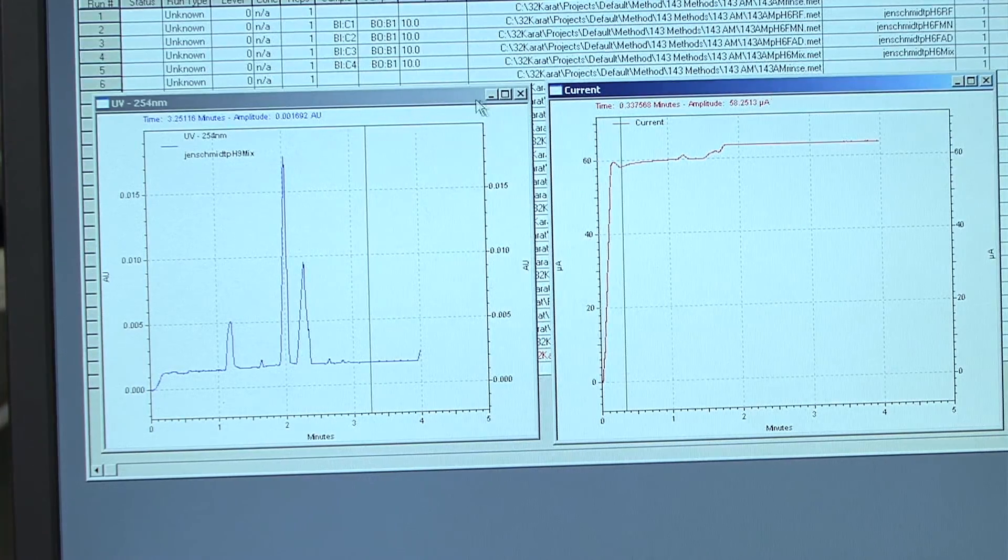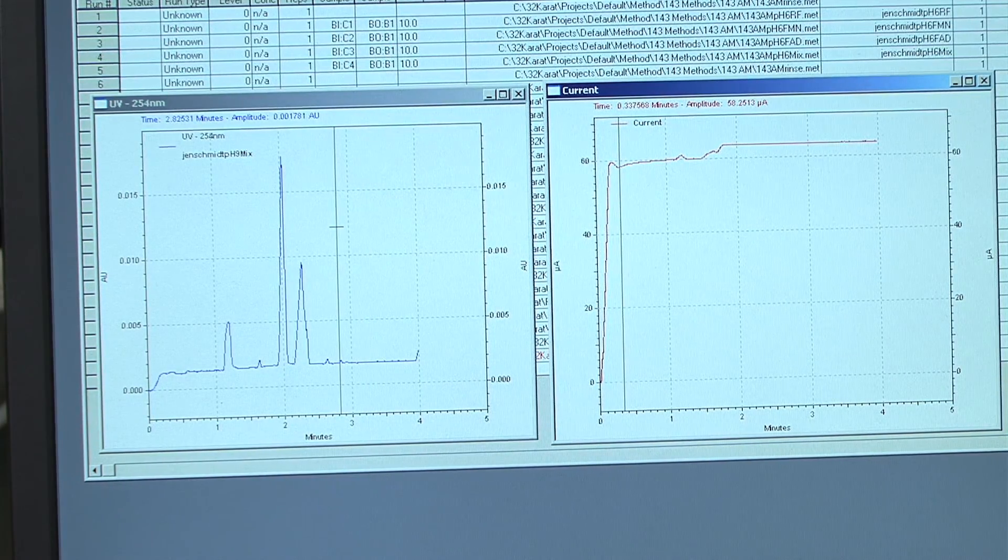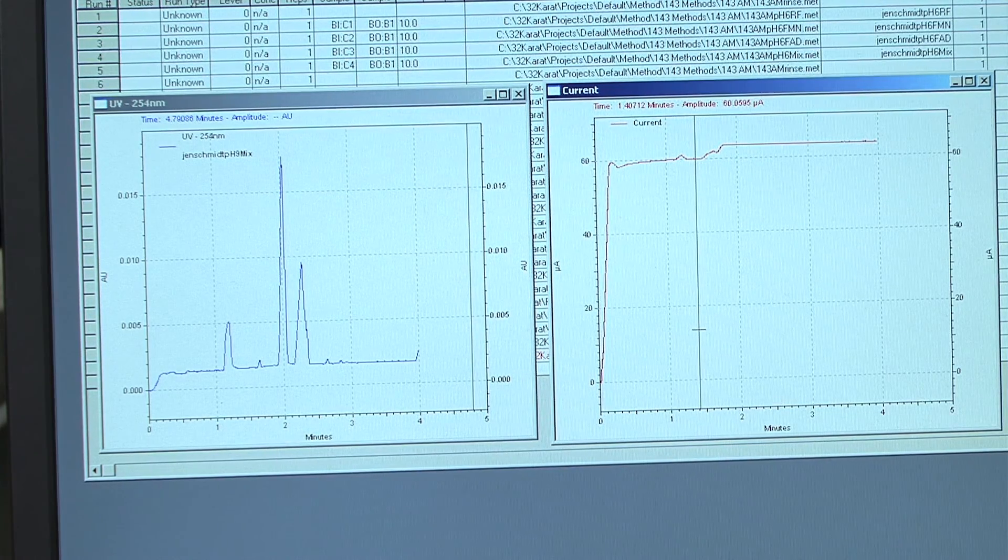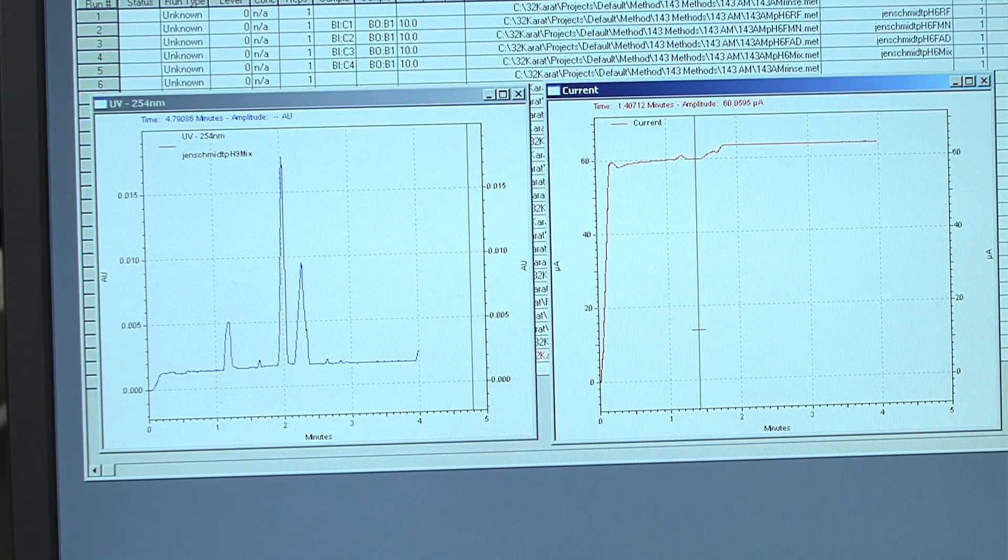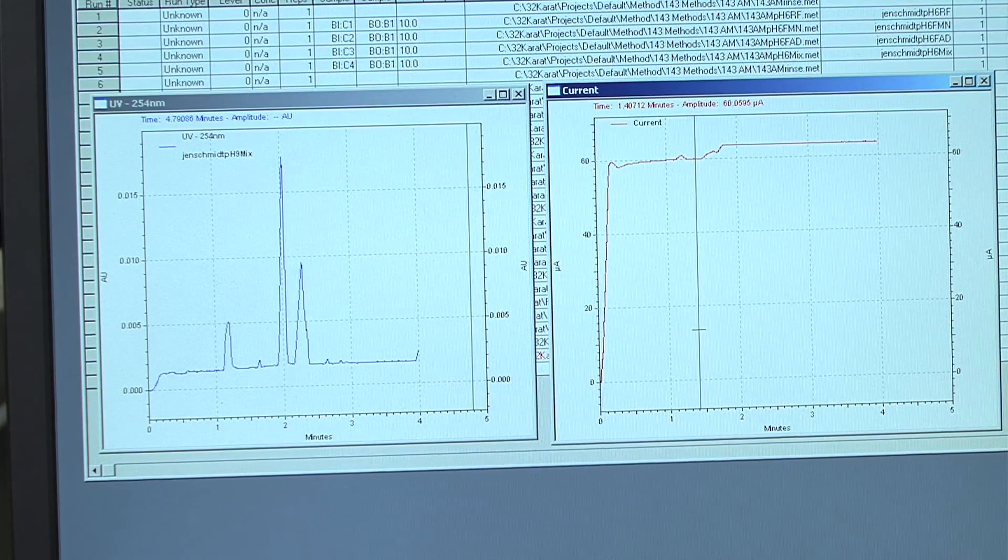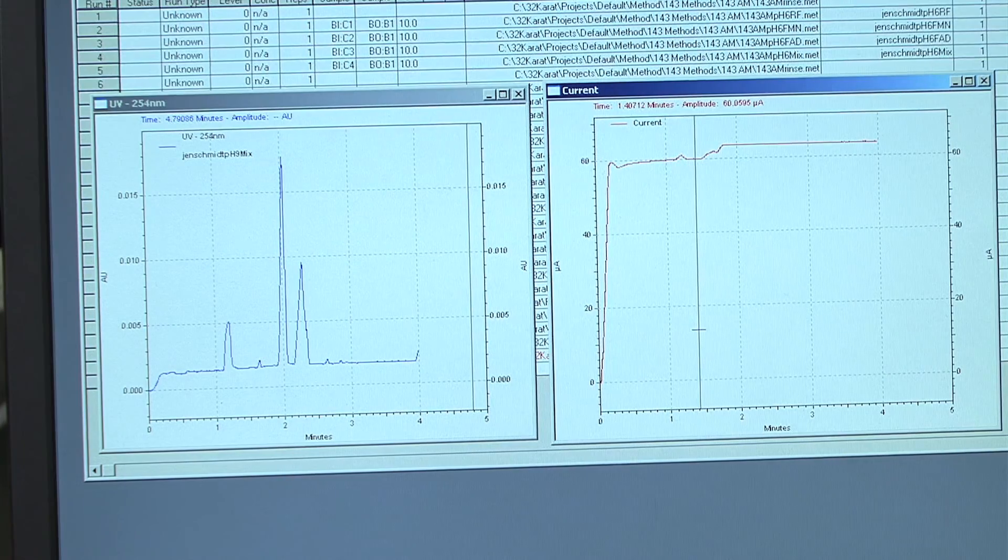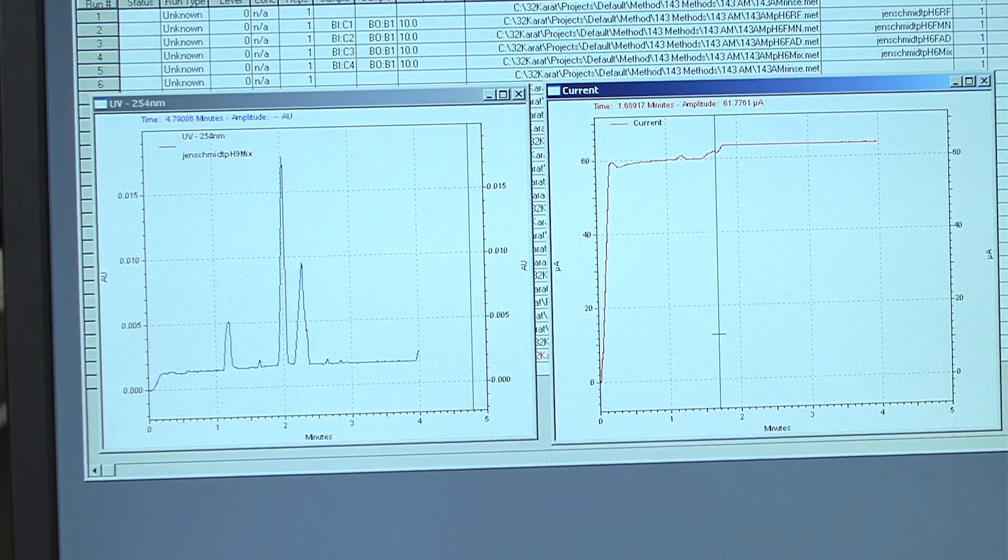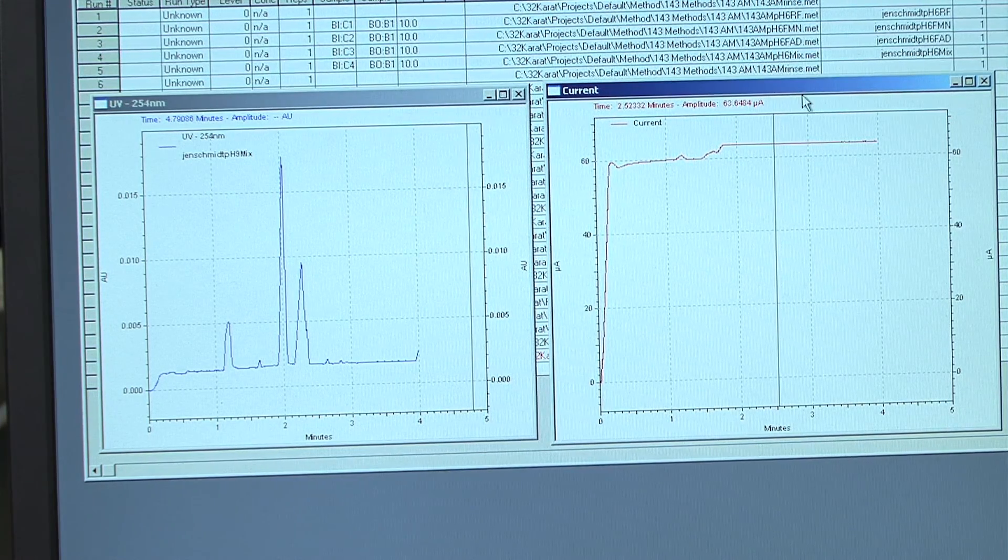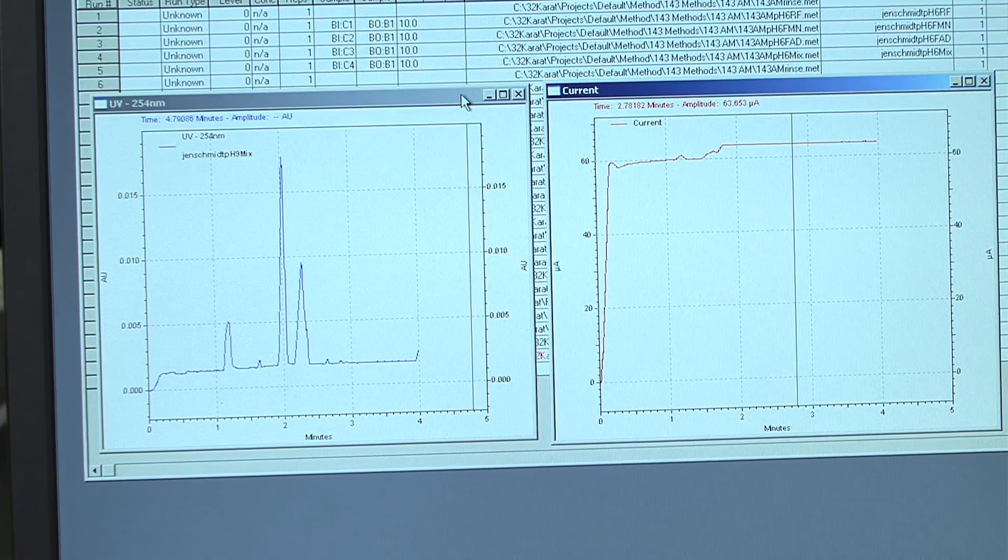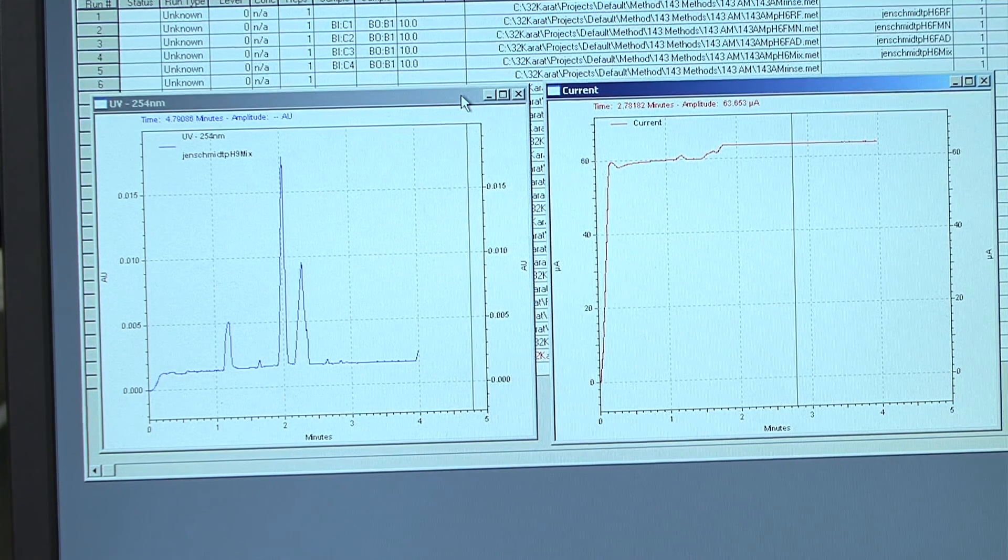So the two windows I have open here are just examples of what your chromatogram will look like and your current versus time plot for the rest of your sequences. Notice that if you remember back to the variable voltage sequence, the current versus time graph kind of looks like a staircase, whereas this one just looks like a flat line almost. If your current versus time graph for the remainder of your sequences looks like this, then that means the instrument is running properly. The electropherogram on the left shows the separation of the mixture containing the three analytes at a pH of 9.